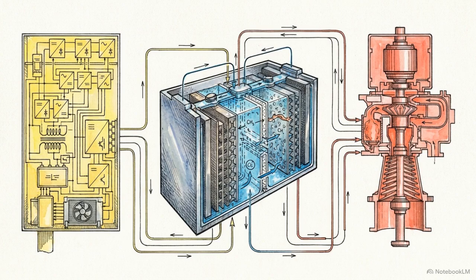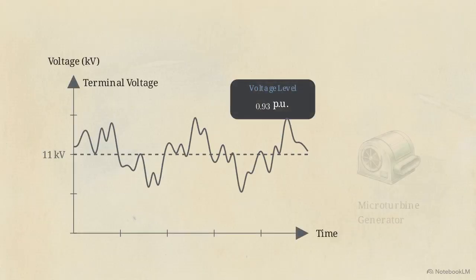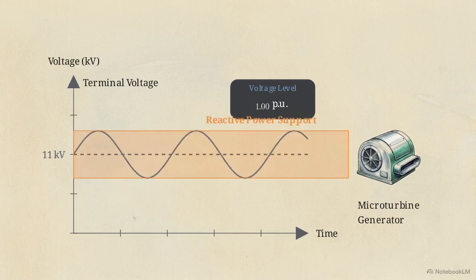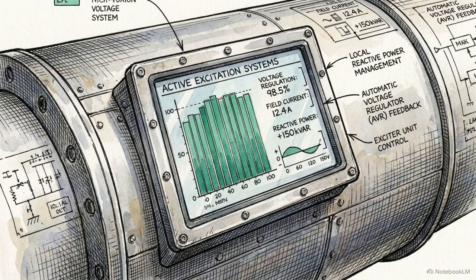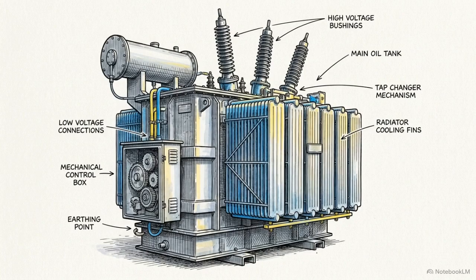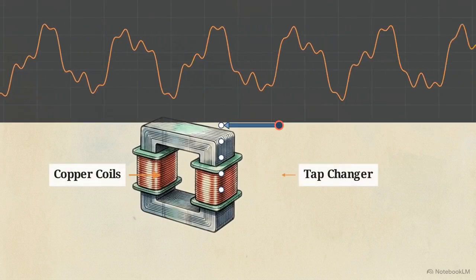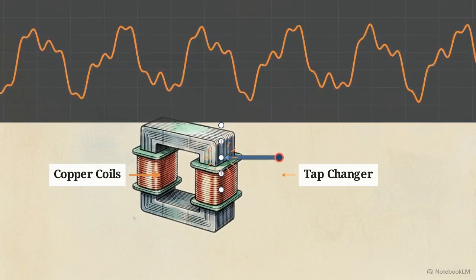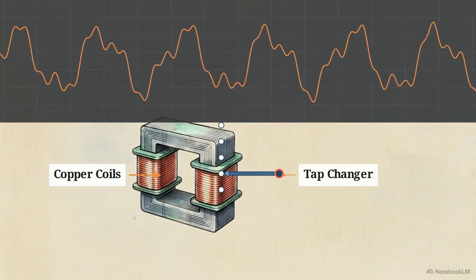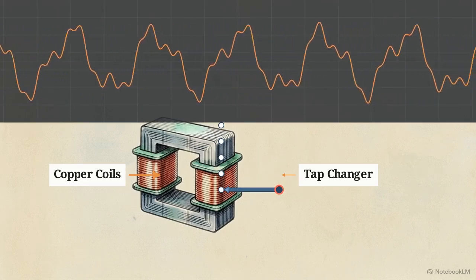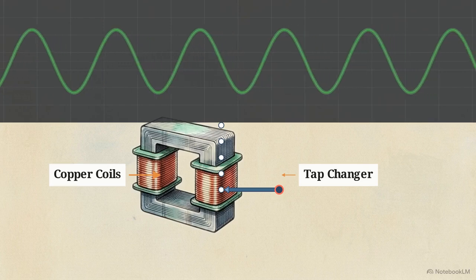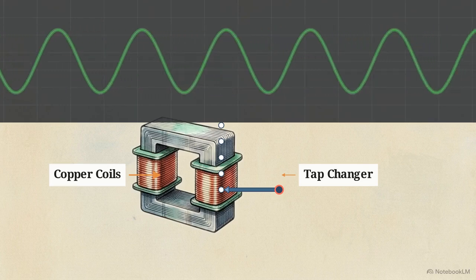the electrical reality. Stable grid operation also requires the management of reactive power to regulate terminal voltages. Local reactive power management is handled electrically by adjusting the excitation systems inside the synchronous microturbines and CHP generators. The mechanical counterpart to that electrical adjustment is the transformer tap changer. Inside the transformer core, a tap changer mechanically shifts to change the number of winding turns. By adjusting this internal ratio, the transformer steps voltage up or down. This forces the output waveform to smooth out and remain consistent at the load nodes despite fluctuations.